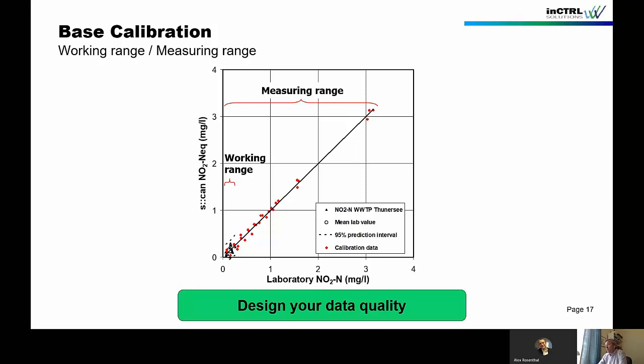0.2 milligram per liter nitrite in the effluent is actually what you target. But that project was about nitrite accumulation, and we wanted to be sure that the instrument is properly measuring up to, let's say, 3 milligram per liter. So we designed a specific experiment, a bucket test, and spiked that bucket with a high concentrated nitrite standard.